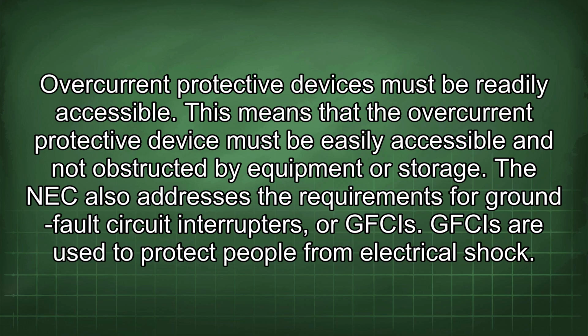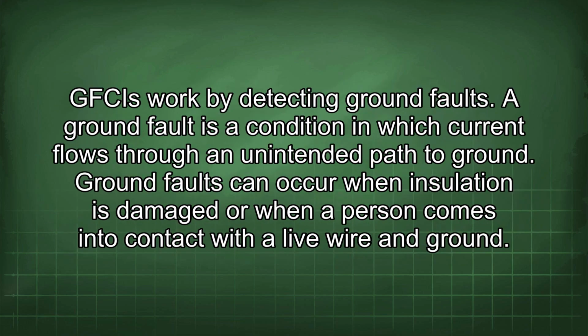The NEC also addresses the requirements for ground fault circuit interrupters, or GFCIs. GFCIs are used to protect people from electrical shock. GFCIs work by detecting ground faults. A ground fault is a condition in which current flows through an unintended path to ground. Ground faults can occur when insulation is damaged or when a person comes into contact with a live wire and ground.